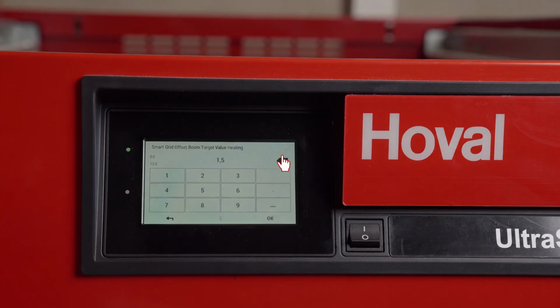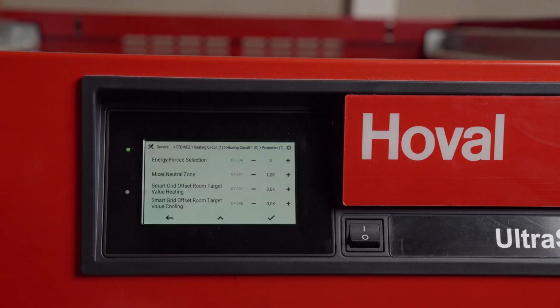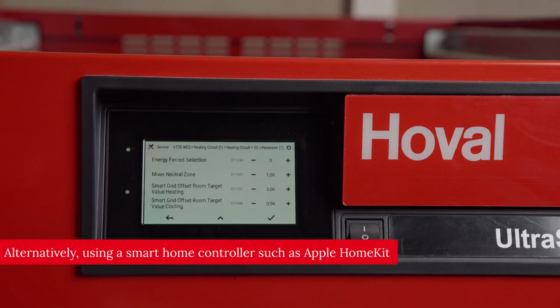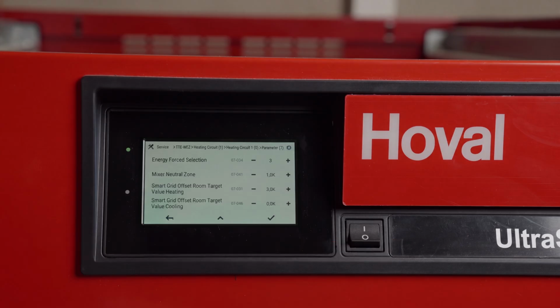for example, 3 Kelvin upon activation. With a standard set point of 20 degrees room temperature, the room temperature is raised to 23 degrees, thereby indirectly increasing the flow temperature, where individual room control can then of course also be activated via Home Assistant, so that the excess power can be stored in the screed or in the building mass.